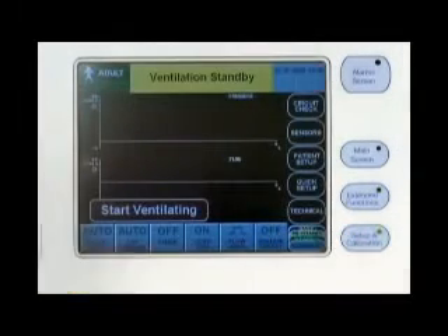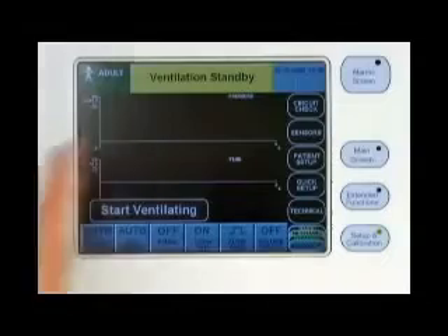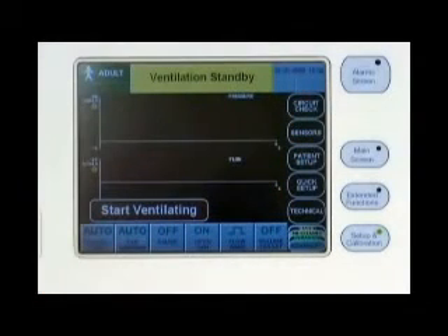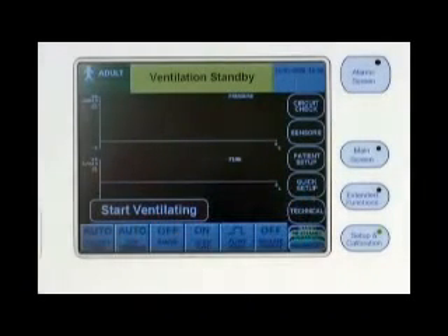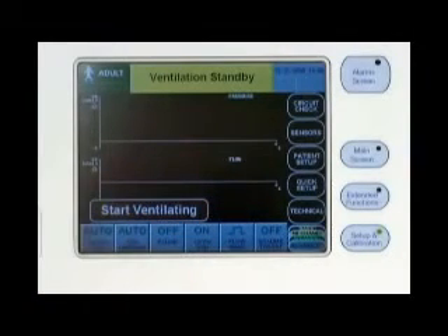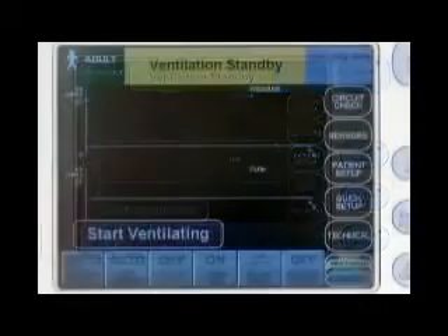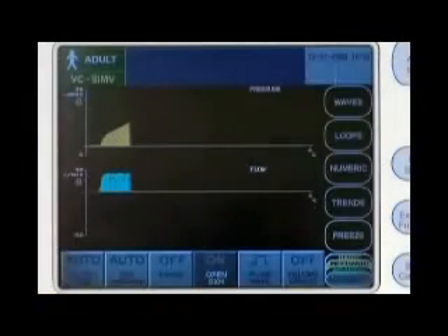The Setup and Calibration menu button allows you to access the circuit check, which can be done only while in standby condition, access the sensor's calibrations, which can be done at any time during standby or ventilation, and access the patient setup and technical setup parameters. The saved screens and event history logs are downloaded from the technical setup screen. I'll touch the Start Ventilating button to begin ventilation.